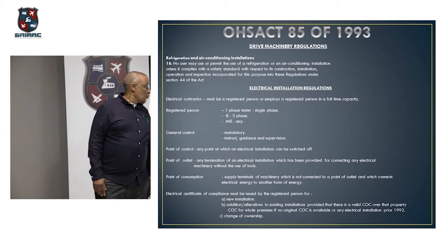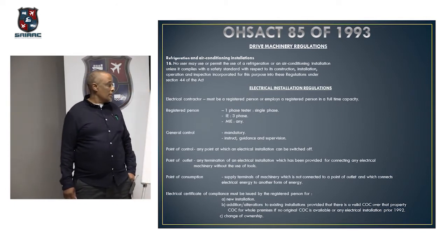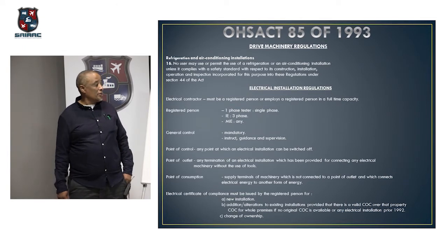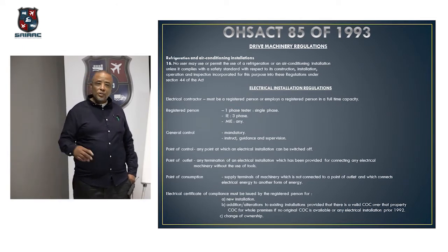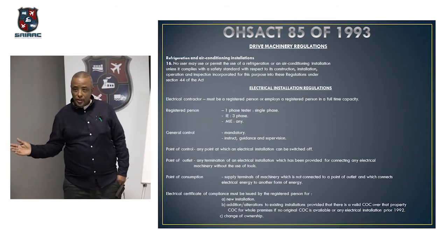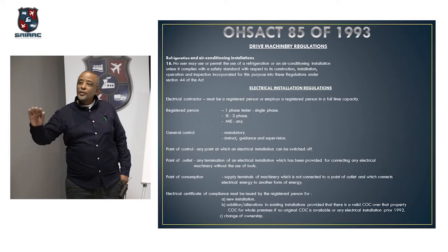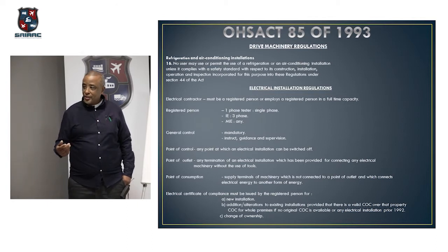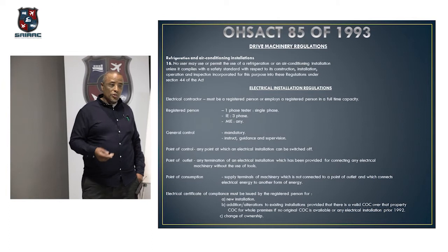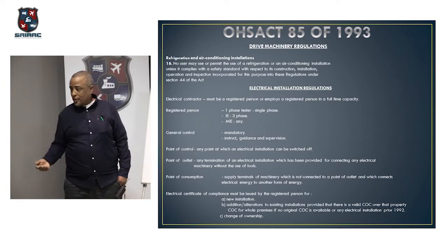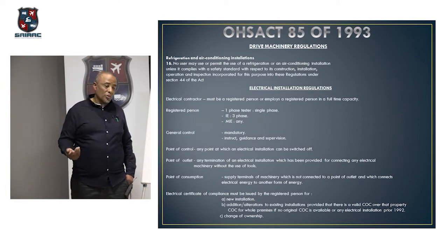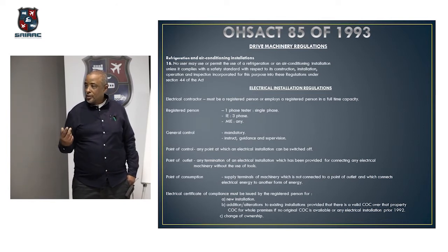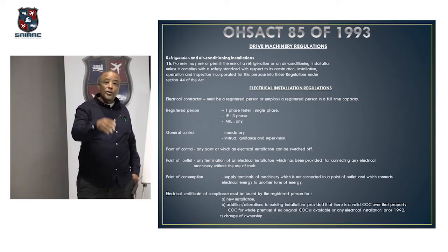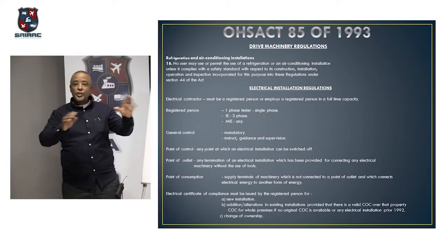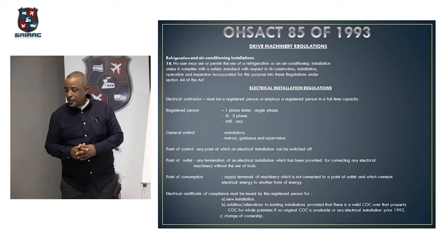All right, and it's also for any alterations to existing installations, provided that there is a COC over their property. Okay, that's also a contentious issue where contractors will go onto a site and do partial work. They'll say, no, I want to give a certificate only for the work that I've done. It doesn't work like that. The first thing a contractor must do is ask the client, do you have a certificate over the property? And they say, no. Well, then unfortunately, I've got to go through your whole property. Be it a factory as well. If you go into a factory and a guy says, no, I just want a couple of machines connected, I need a COC, please.